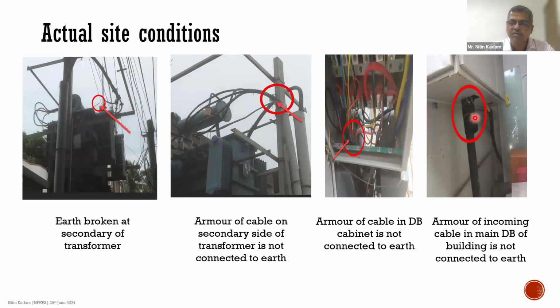And if you talk to the distribution company technicians, they say this is how we do it. We don't want to connect it to the panels. And if this is done, there is no earthing coming right from the distribution transformer to this panel. And we might think that there is earthing available to the elevator, but actually it is not. So it will be an open connection. And if there is a local site earthing done, you are actually converting that elevator installation to a TT network.